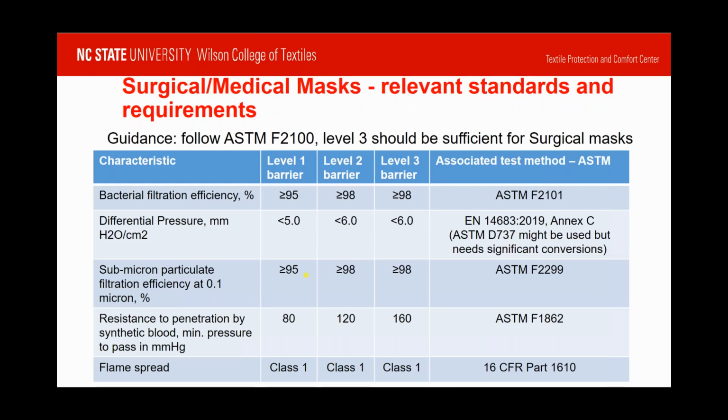So here is pretty much a copy of the documentation from the ASTM F2100 standard. Level 3 is the highest level here, so you can consider that as a surgical mask. It's a material filtration efficiency test.